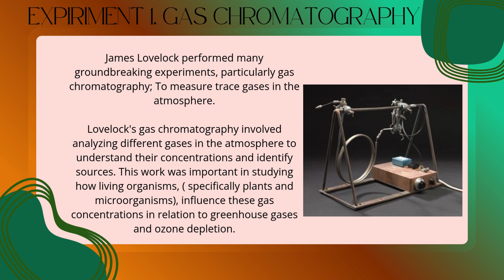So the gas chromatograph was a device that separates and measures specific gases. It uses a carrier gas, often helium or nitrogen, to transport the sample through a column that contains stationary phase materials. Secondly, there would be a sample injection. Air samples are injected into the machine where they mix with the carrier gas. Thirdly, separation. As the gases travel through the column, they separate based on their physical and chemical properties. And lastly, after separation, gases pass through a detector that measures their concentration and outputs data for analysis.